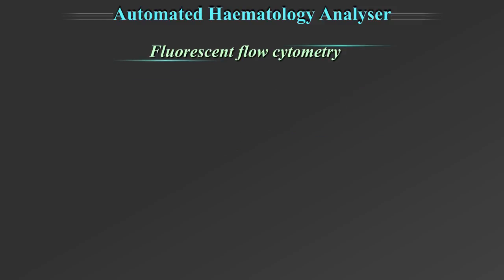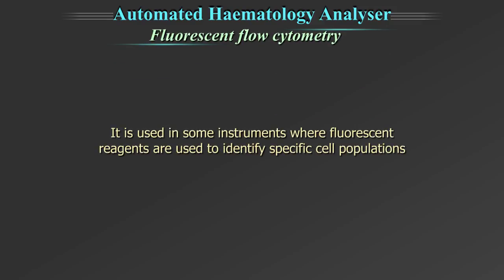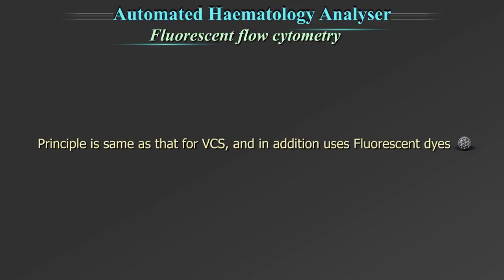Fluorescent flow cytometry is used in some instruments where fluorescent reagents are used to identify specific cell populations. The principle is the same as that for volume conductivity scatter, and in addition, it uses fluorescent dyes to reveal the nucleus-to-plasma ratio of each stained cell. The added advantage is the analysis of platelets, nucleated RBCs, and reticulocytes.